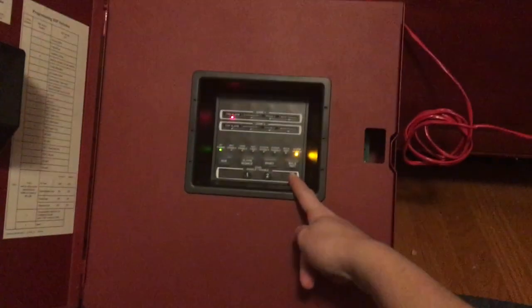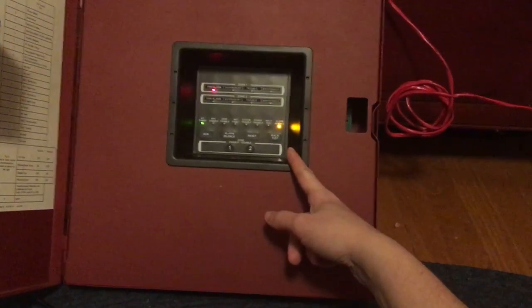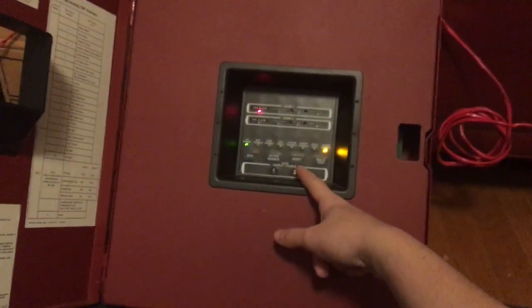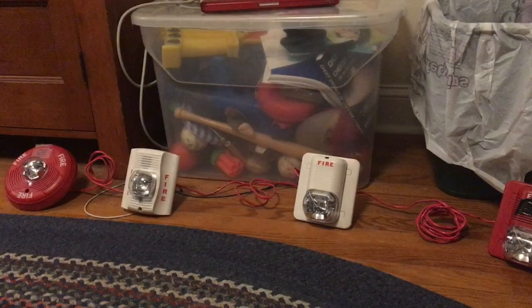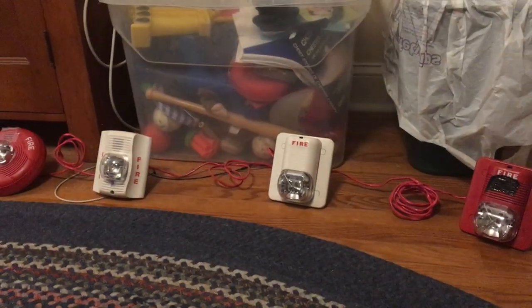When you set the panel to selective silence, as well as either System Sensor Sync, Gentex Sync, or Wheelock Sync depending on which brand you're using, it also has the ability to silence all of these horn strobes using the same pair of wires. It doesn't matter how many devices you hook up — it'll still sync and silence everything, provided it's running on a single pair of wires.